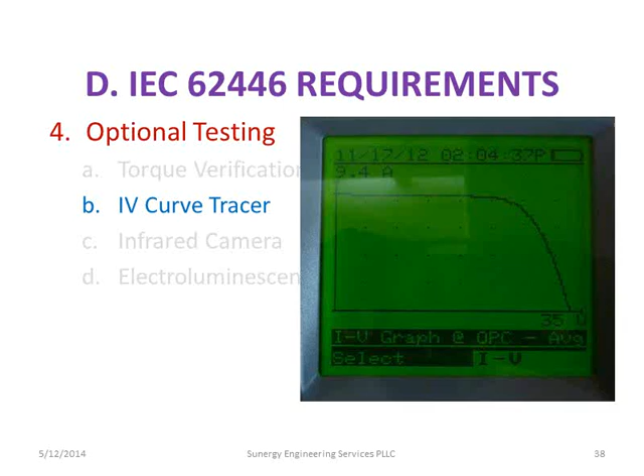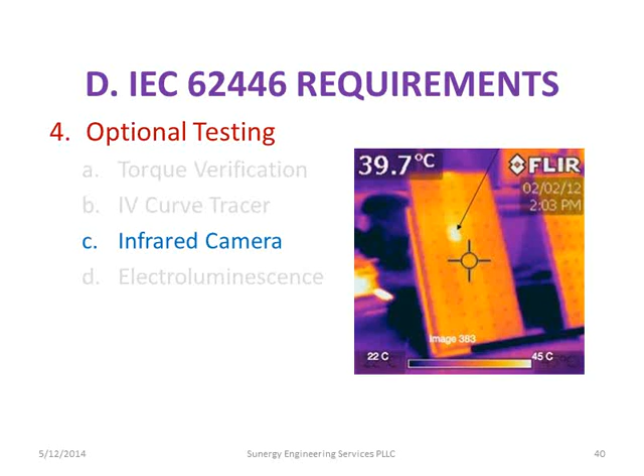And an infrared camera is more or less a troubleshooting tool when you have problems. In this case right here, that cell is actually a shaded cell that's hot right there. And that's why it's so hot. It's actually dissipating energy from the rest of the module. And it's not enough energy to fire the diode, but it's enough energy for it to be quite a bit hotter. So it's running at about 10, 15 C hotter, maybe.